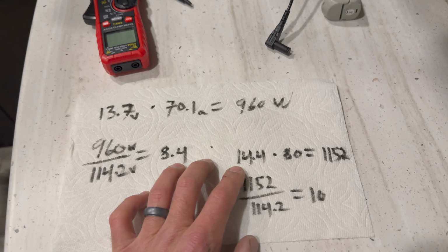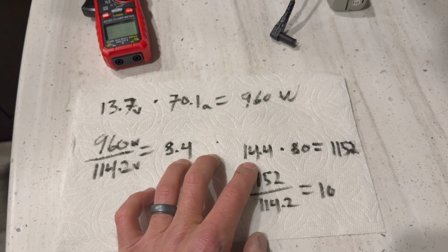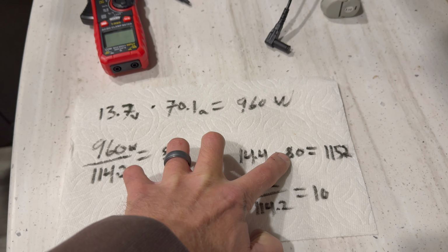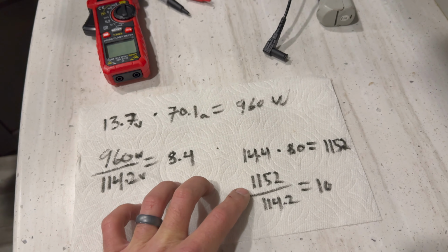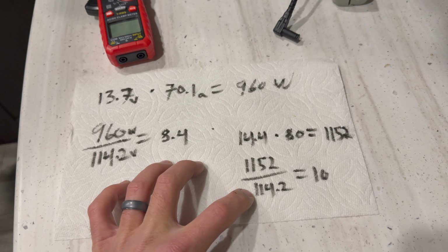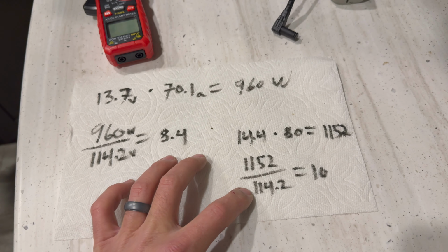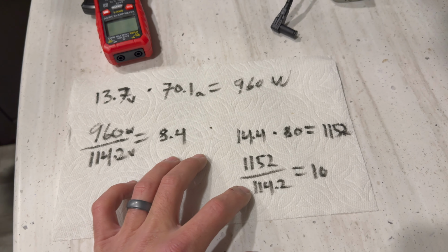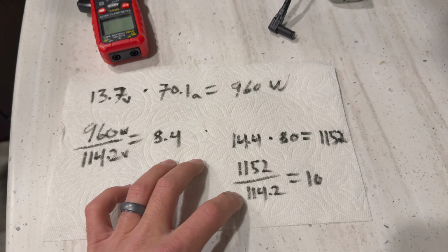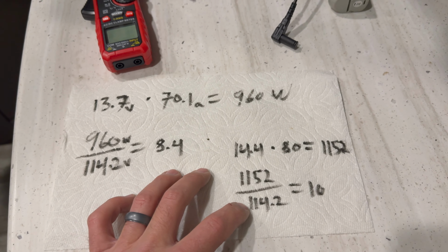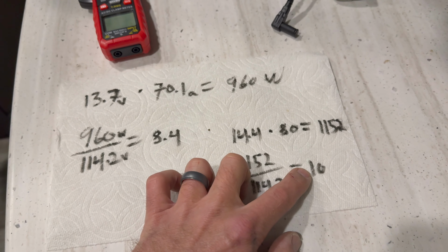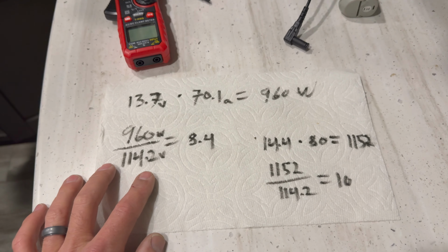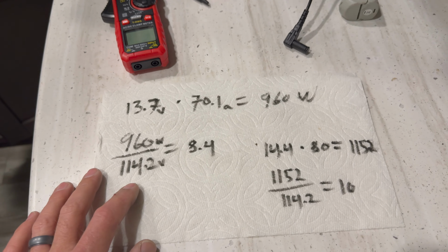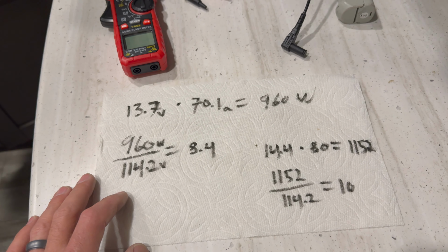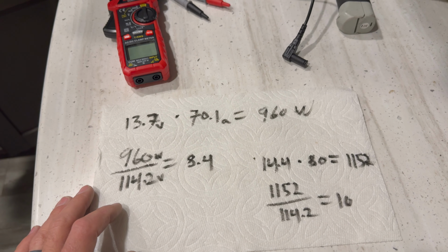But even at maximum capacity, if we had 14.4 volts running at 80 amps, which would probably never happen, it should be 1152 watts. And 1152 divided by the same 114.2 -- I know in most scenarios it should be 115 or 120 depending on your housing circuit, but this is what we measured, 114.2 -- anyway, should be maximum 10 amps. But nonetheless, I measured between 14.8 and 15.2. So yeah, we'll just go ahead and switch it out to avoid any problems.